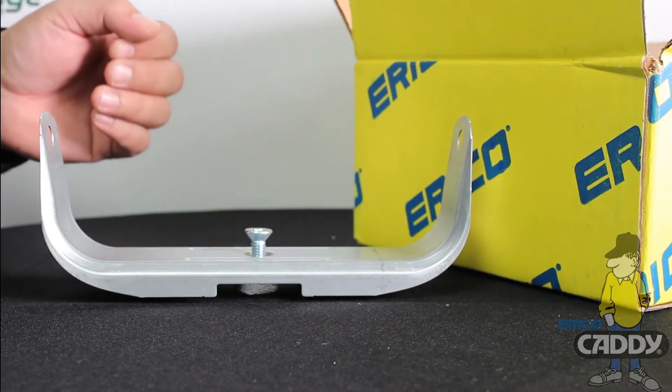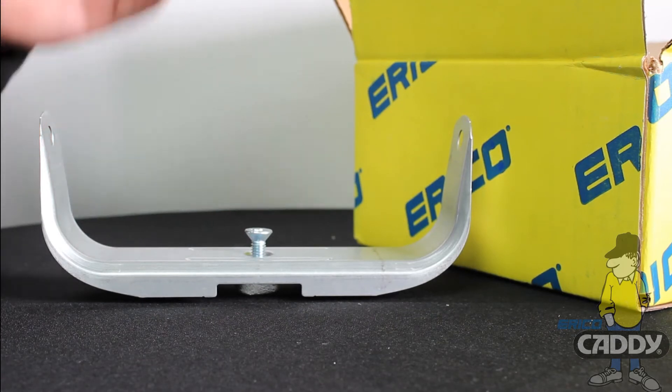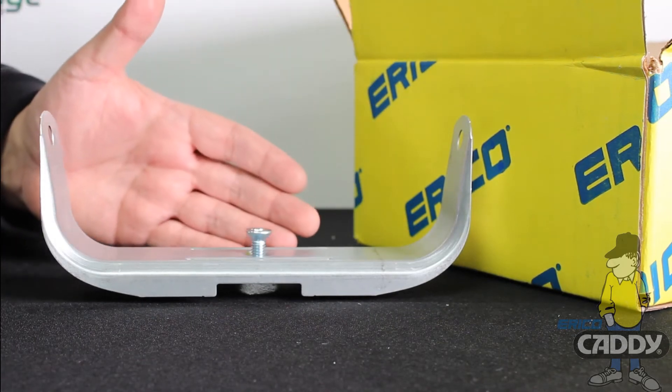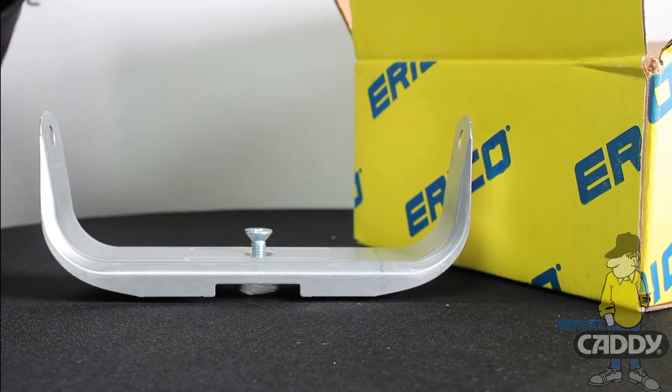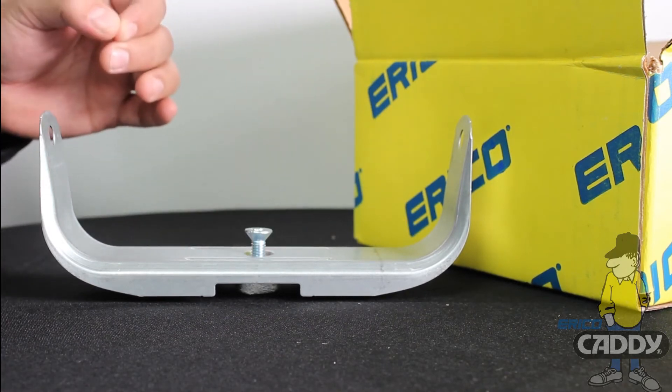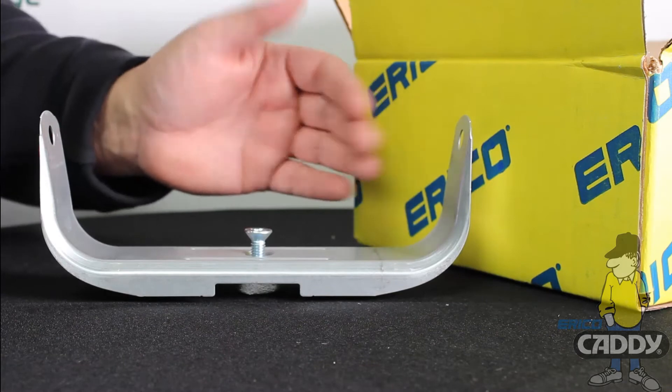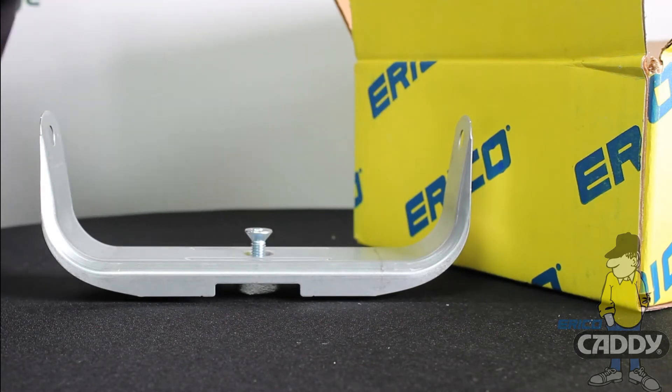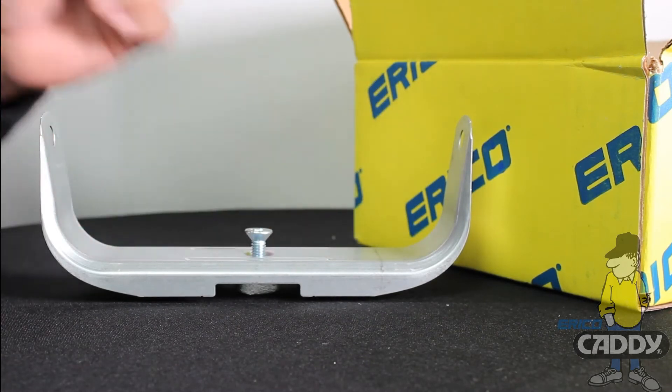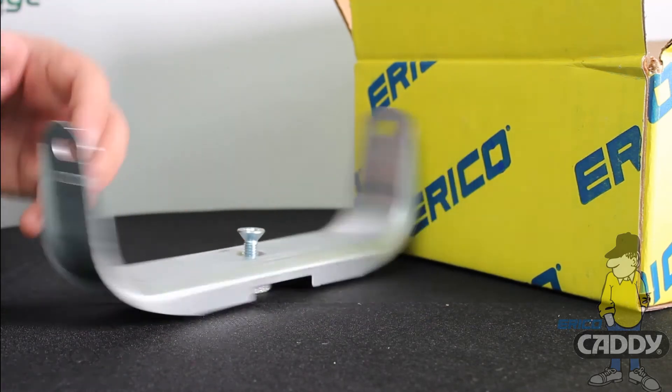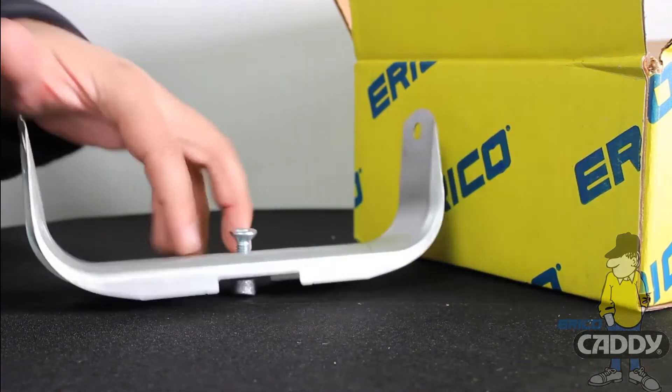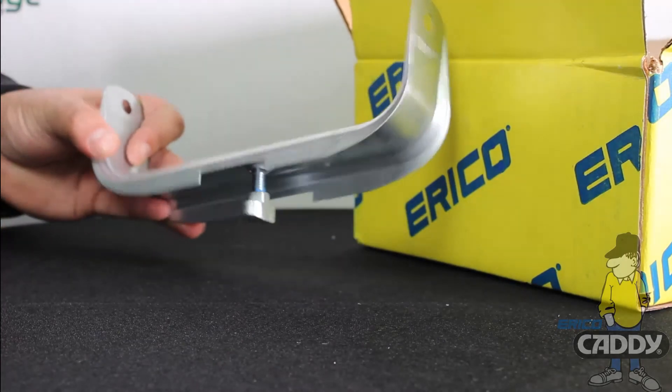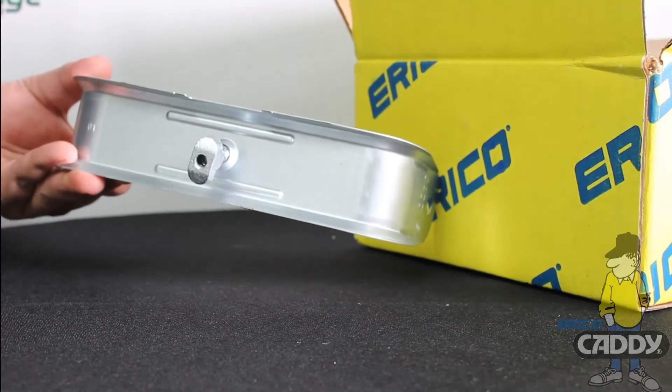This is the 200; the other one's the 300. The 200 on strut will support 320 CAT5E cables or 200 CAT6. If you use the same size for rod or cantilever support, it will support 500 CAT5E or 315 CAT6. Let's check out the associated parts.